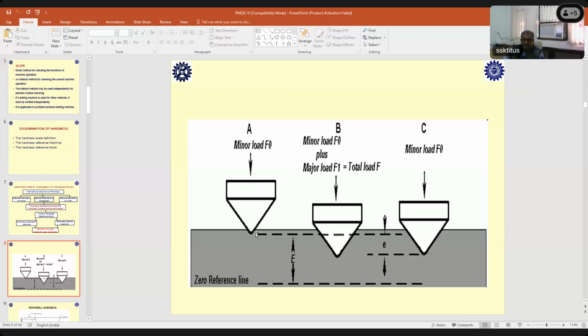Then you have to wait. You have to apply this force as per the timing cycle defined in the standard, so within 1 to 8 seconds you have to apply it. Then after that you have to apply some additional test force, which is sometimes 50 kg, sometimes 90 kg, sometimes 140 kg. If you apply 50 kg, the total force is going to be 60 kg. If you apply 90 kg, the total force is going to be 100 kg. And if you apply 140 kg additional force, the total is going to be 150 kg. It's already written here. These three scales make the A, B, C scales with the diamond indenter.